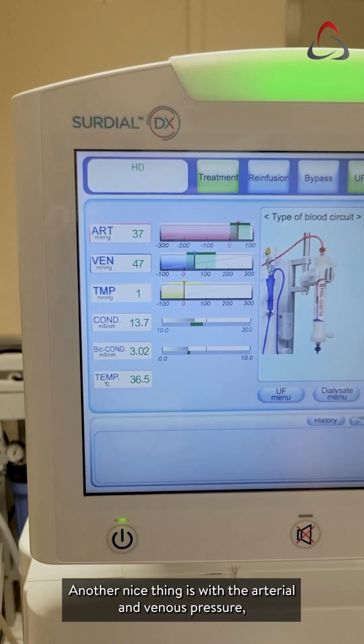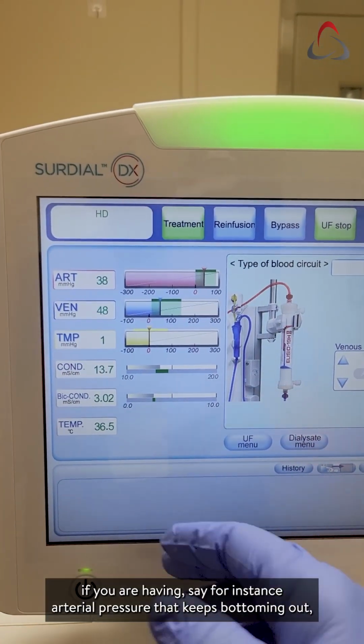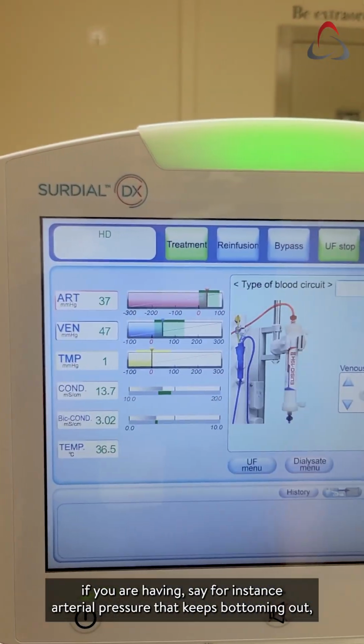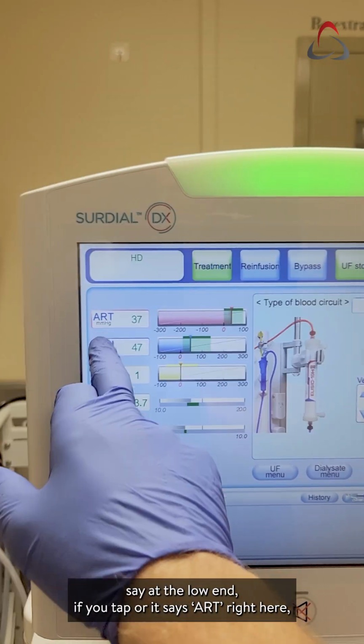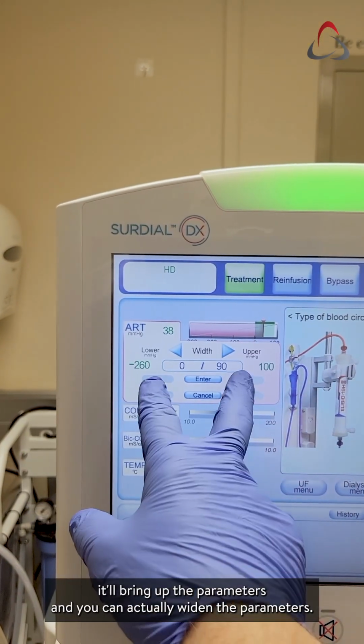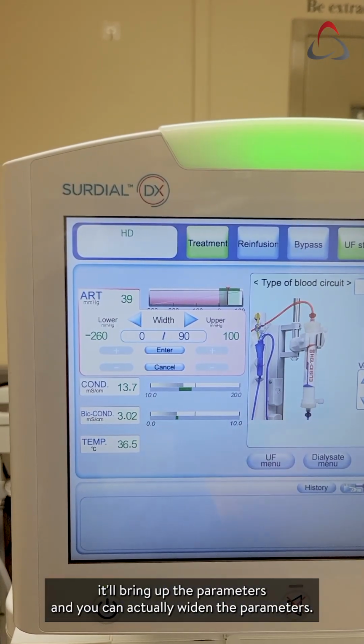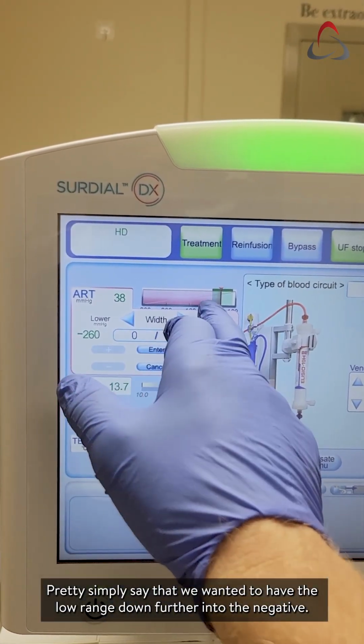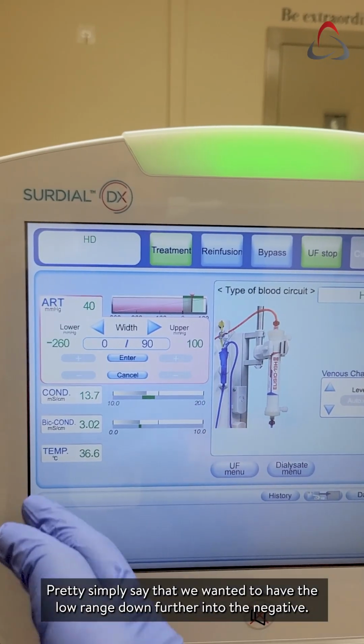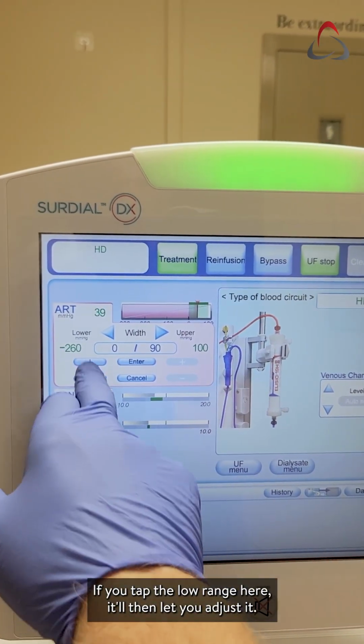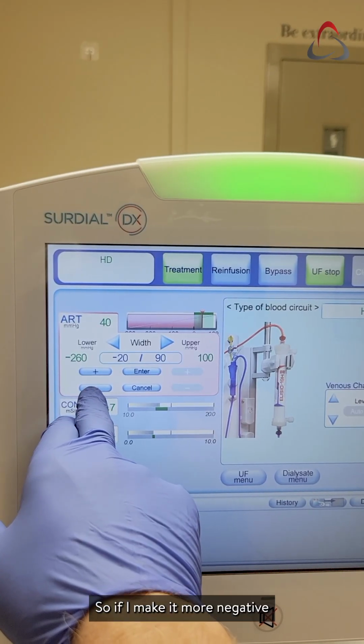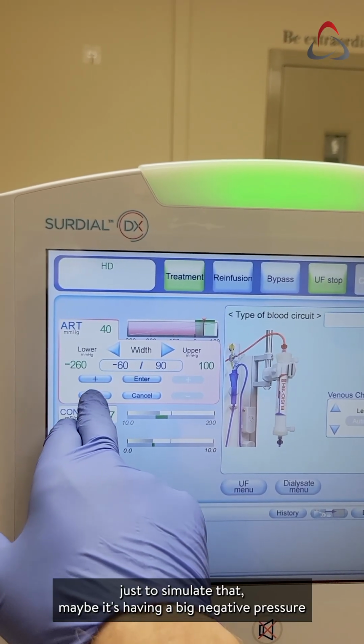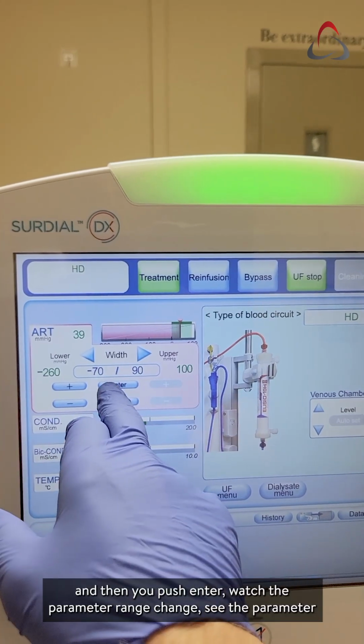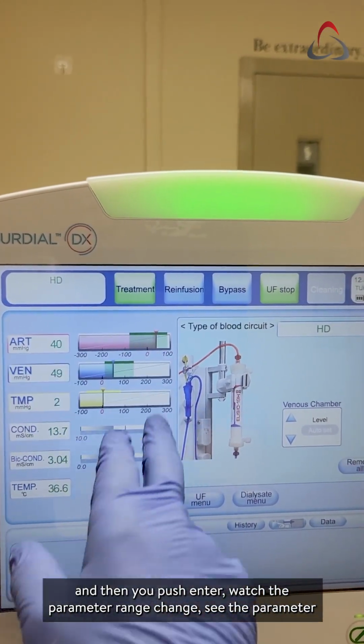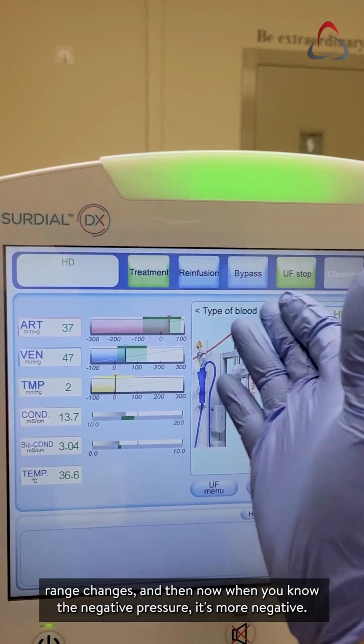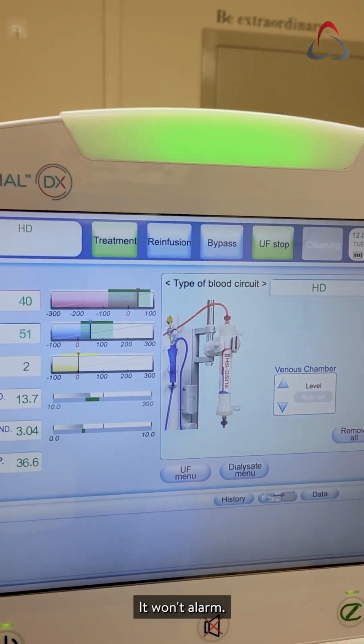Another nice thing is with the arterial and venous pressure. If you are having, say, arterial pressure that keeps bottoming out at the low end, if you tap where it says ART right here, it brings up the parameters and you can widen them pretty simply. Say we wanted the low range down further into the negative. If you tap the low range here, it lets you adjust it. So if I make it more negative, just to simulate a big negative pressure, and then push enter, watch the parameter range change. See the parameter range changes? Now when the negative pressure gets more negative, it won't alarm.